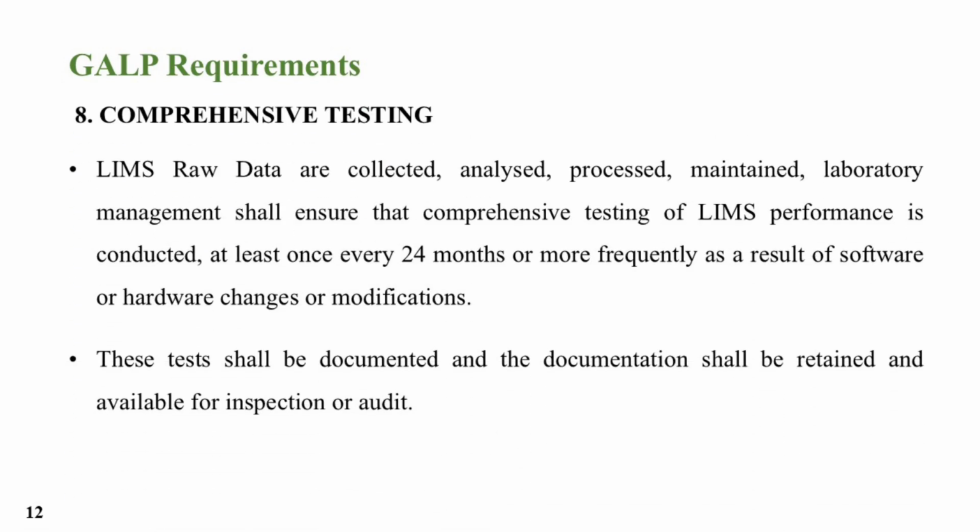The LIMS system must be tested regularly. This is done at least once every 2 years, or whenever changes are made. Testing ensures that the system is still working correctly and giving accurate results.